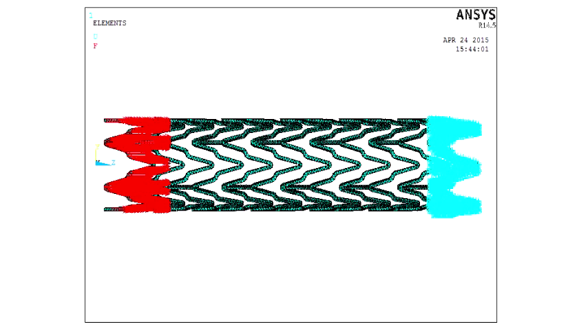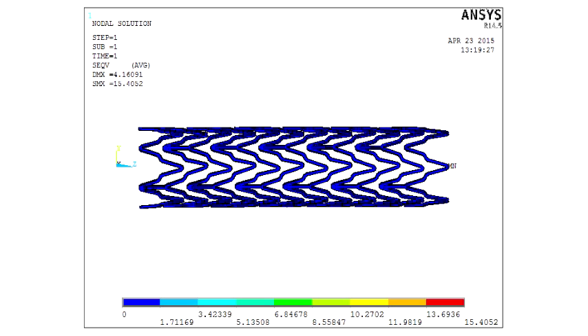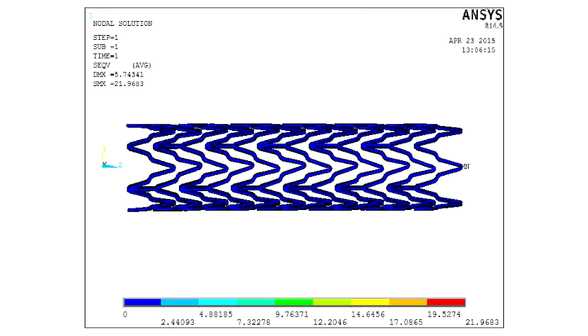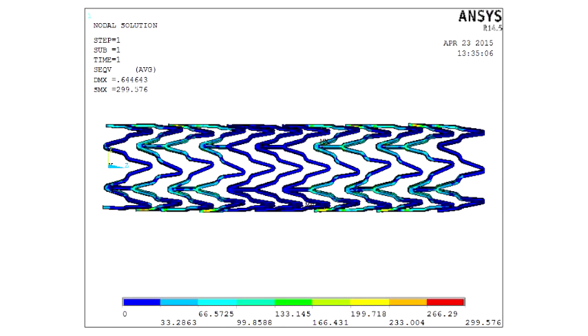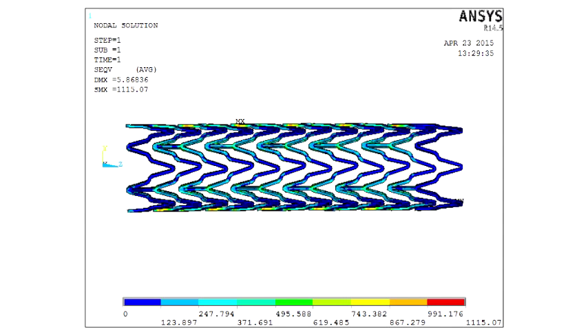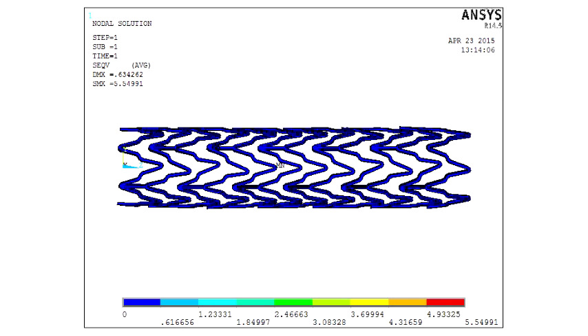In the ANSYS model, both the coated-and-treated metal properties and the bare metal properties were used, applying loads of 5 N and 10 N. The coated and treated metal showed significantly lower stress compared to the bare metal, demonstrating that our synthesized stent material is completely compatible for stent design, especially comparable to nitinol.